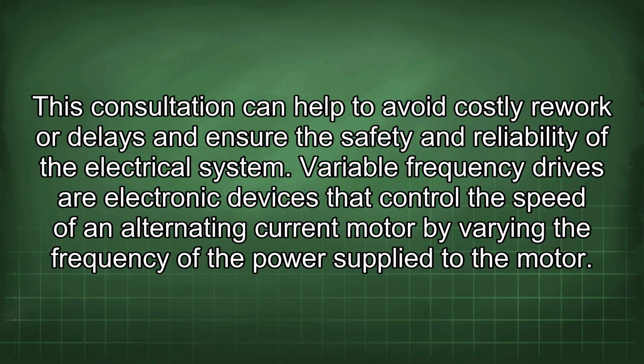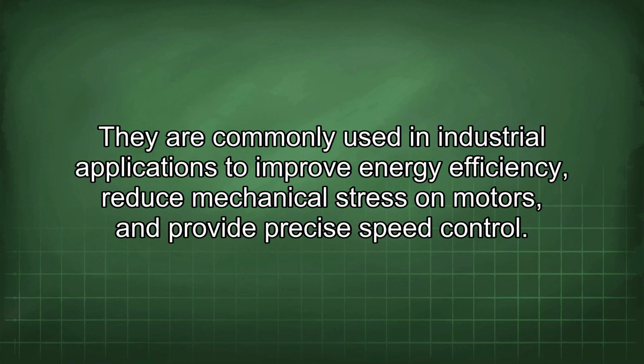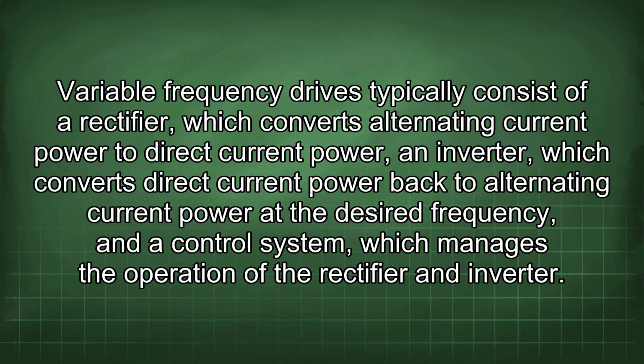Variable frequency drives are electronic devices that control the speed of an alternating current motor by varying the frequency of the power supplied to the motor. They are commonly used in industrial applications to improve energy efficiency, reduce mechanical stress on motors, and provide precise speed control. Variable frequency drives typically consist of a rectifier, which converts alternating current power to direct current power, an inverter, which converts direct current power back to alternating current power at the desired frequency, and a control system, which manages the operation of the rectifier and inverter.